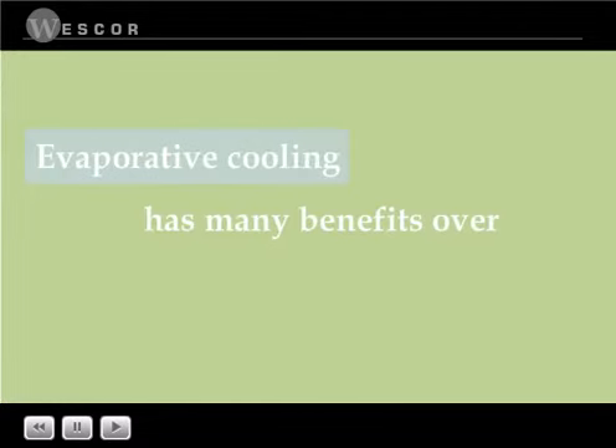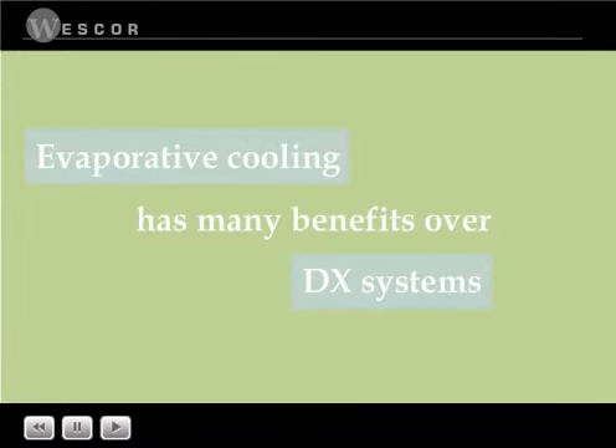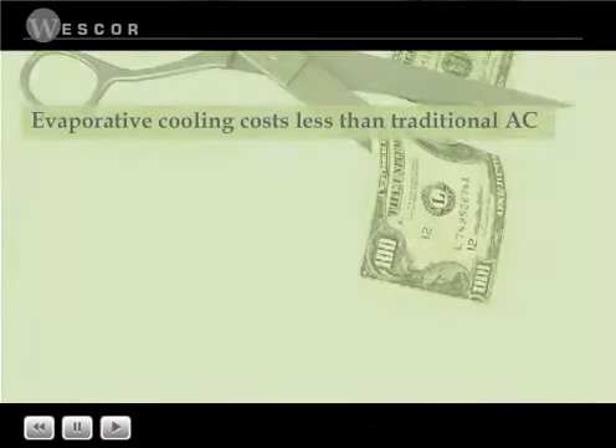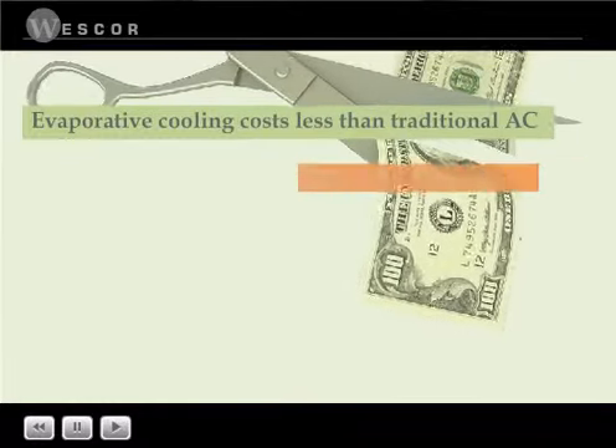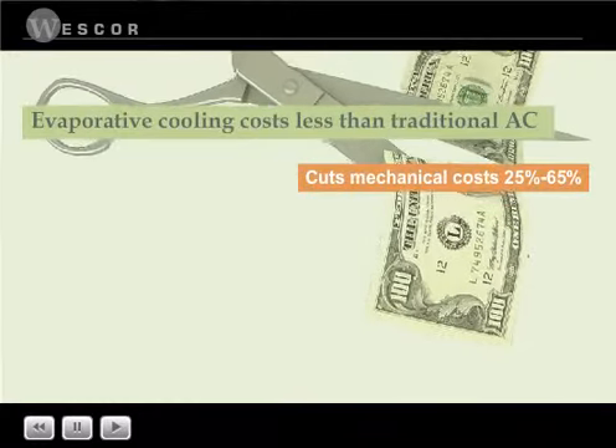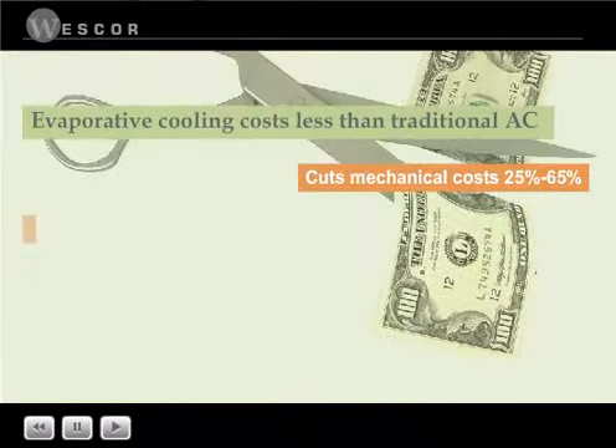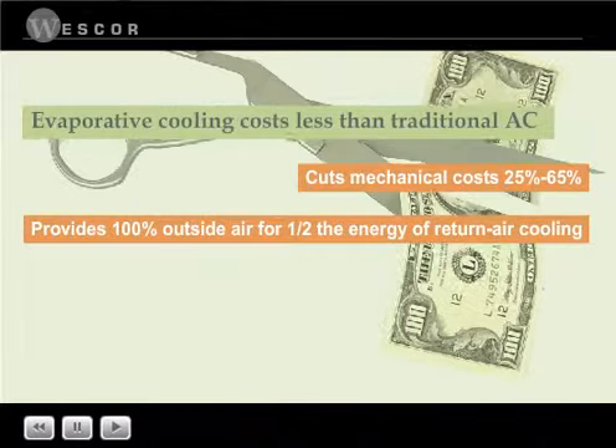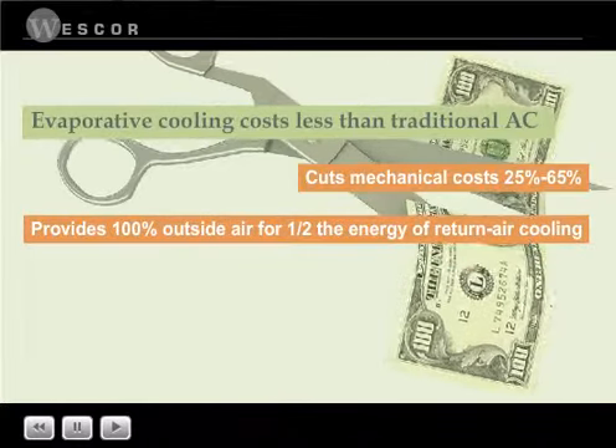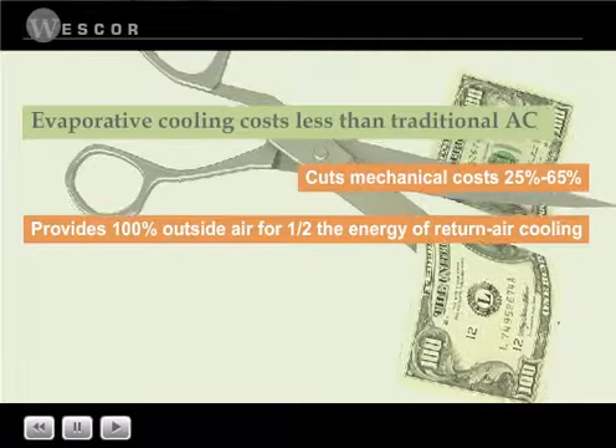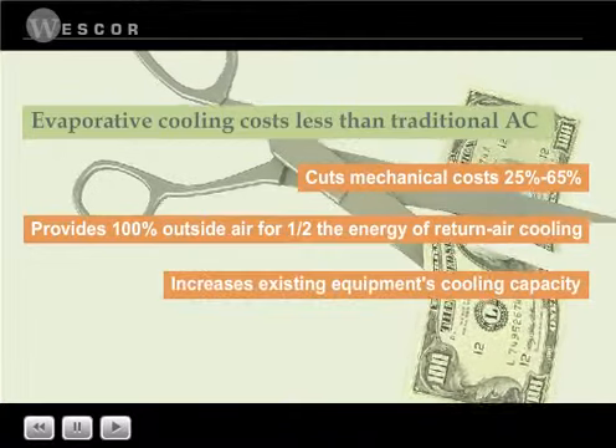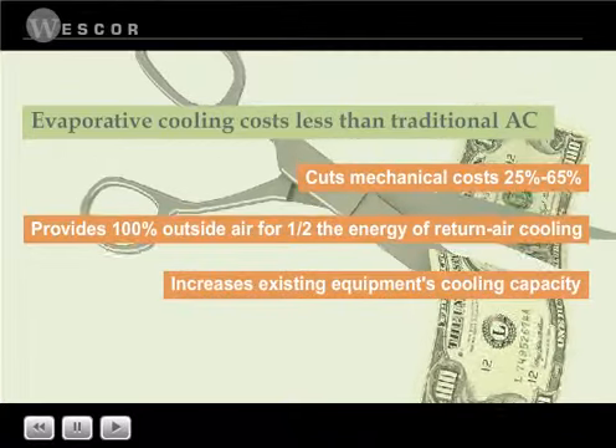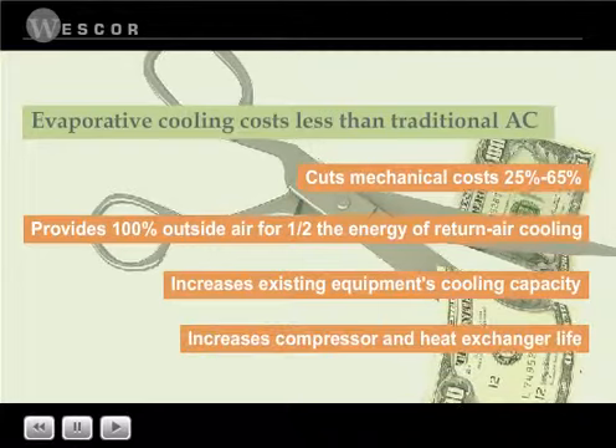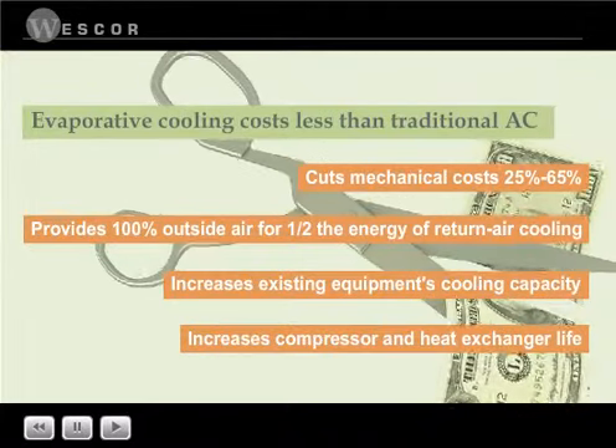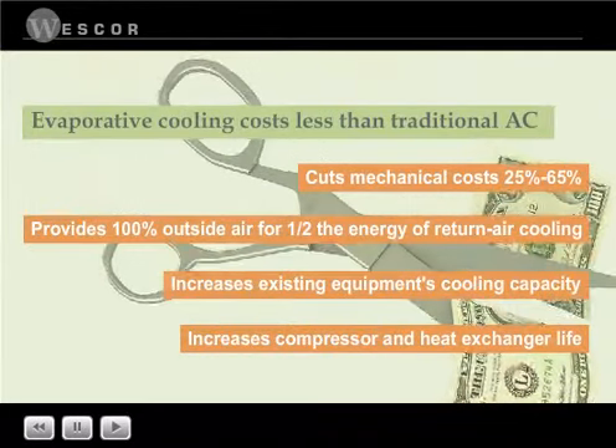Now that we know how evaporative cooling works, let's look at its many benefits. Evaporative cooling costs less than traditional air conditioning. It generally cuts mechanical equipment costs 25 to 65%. It provides 100% outside air cooling at less than half the energy cost of mechanical equipment's return air cooling, increases existing equipment cooling capacities without adding mechanical cooling, and increases compressor and heat exchanger life when used in conjunction with DX.